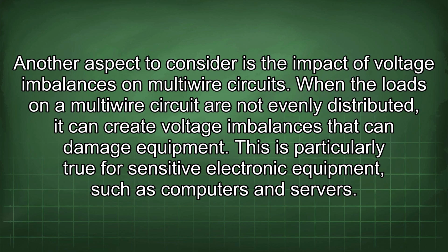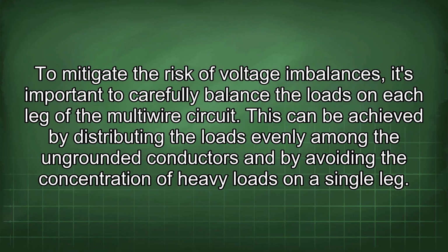Another aspect to consider is the impact of voltage imbalances on multi-wire circuits. When the loads on a multi-wire circuit are not evenly distributed, it can create voltage imbalances that can damage equipment. This is particularly true for sensitive electronic equipment, such as computers and servers. To mitigate the risk of voltage imbalances, it's important to carefully balance the loads on each leg of the multi-wire circuit. This can be achieved by distributing the loads evenly among the ungrounded conductors and by avoiding the concentration of heavy loads on a single leg.